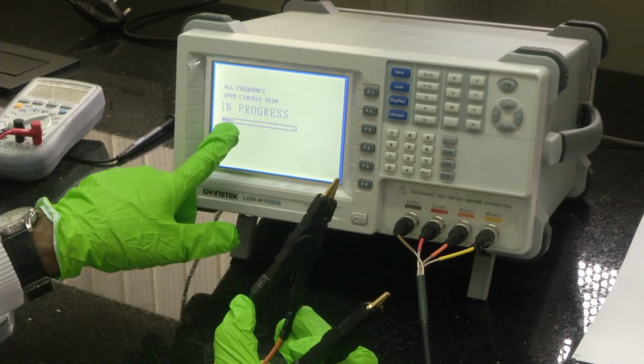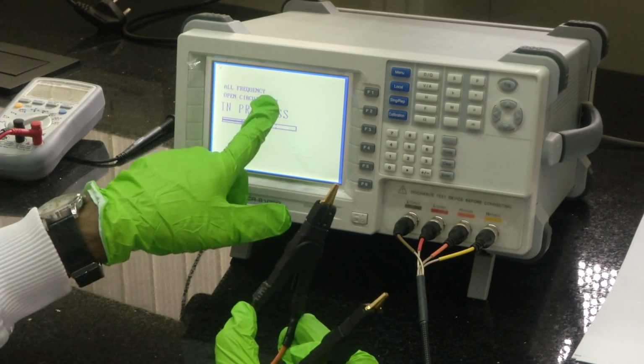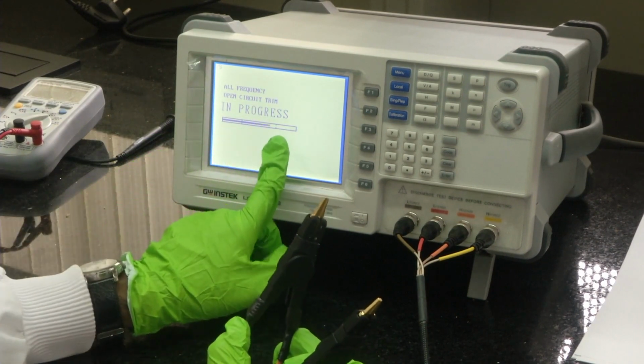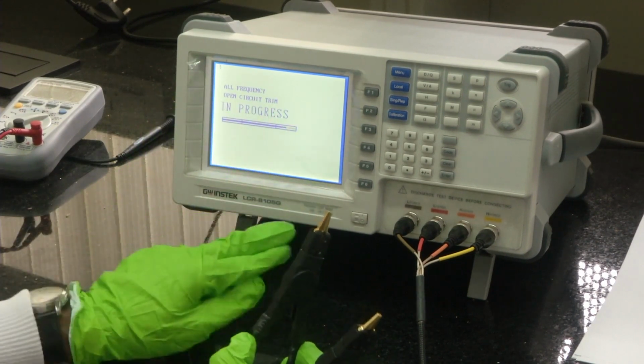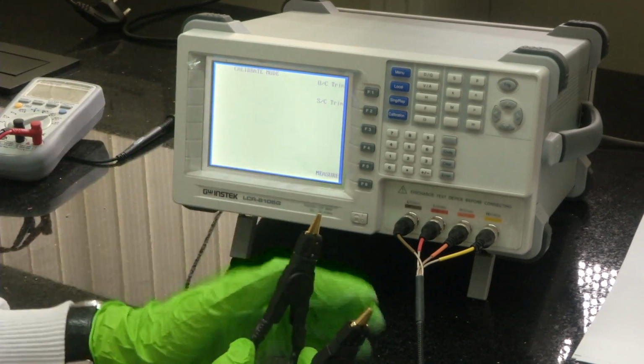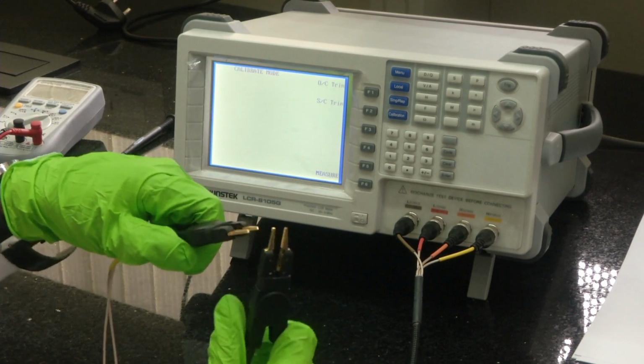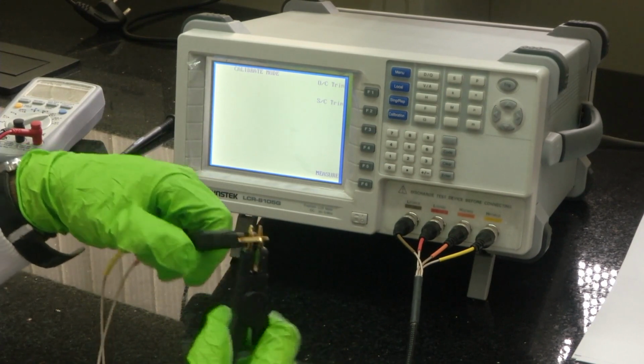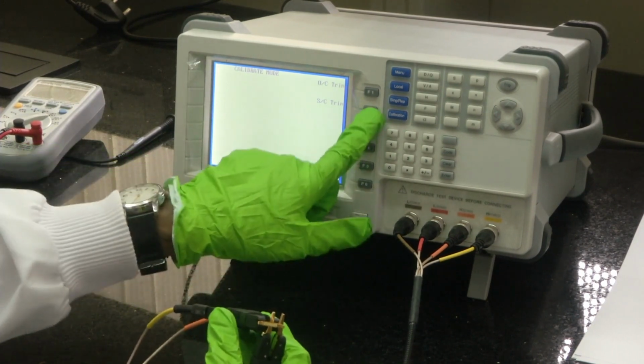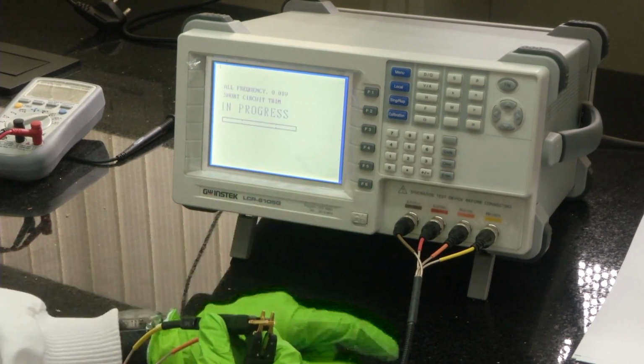So, you see the progress bar, because it is an all frequency calibration, that is why it is taking time. It is trying to calibrate across the entire spectrum of frequencies that the equipment can handle. It has succeeded. Now, we have to do short circuit trim. So, before we do short circuit trim, we have to actually short the probes. So, we have shorted the probes, click short circuit trim, all frequencies.